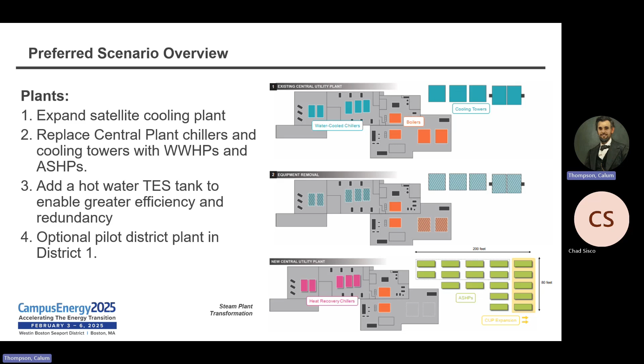That will allow the existing main central plant to remove and decommission its chillers, freeing up space for new water-to-water heat pumps and heat recovery chillers. Then it starts simultaneously generating heating and cooling from the central plant. Finally, we'll look to add additional air source heat pumps outside and adjacent to the existing central plant, which can handle the top-up heating requirements of the future system.